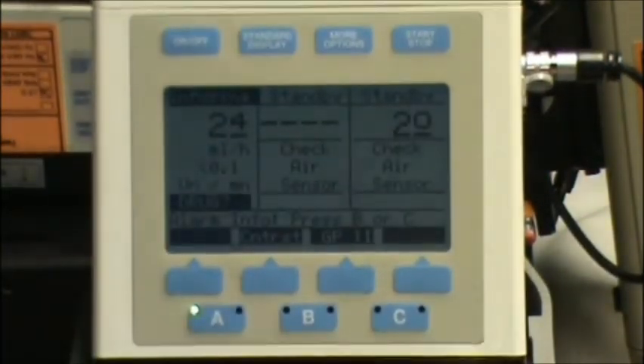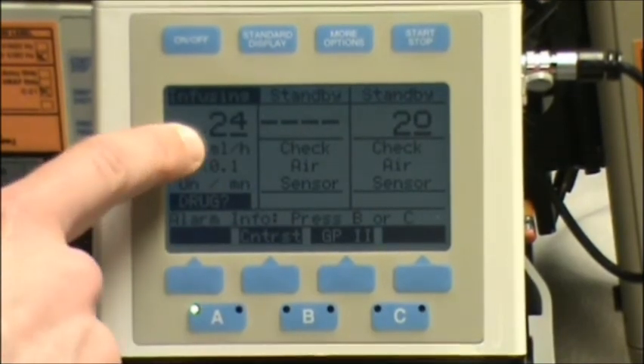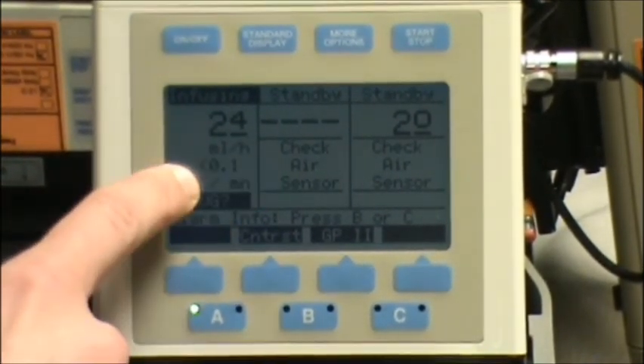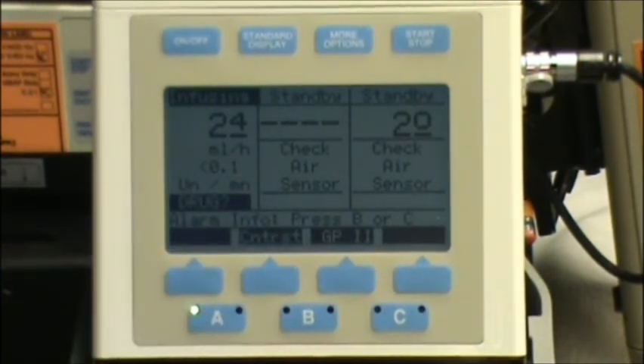Back to standard display. Now my channel A says that I'm infusing at 24 mLs an hour at less than .1 unit a minute. And that's how to program vasopressin into the triple channel pump.